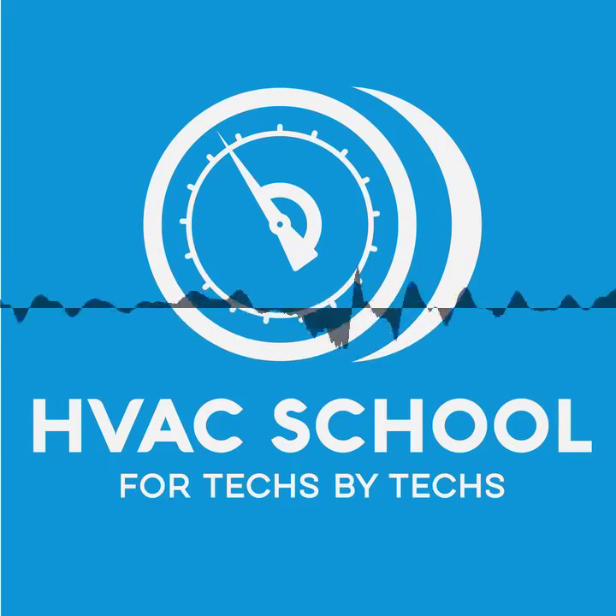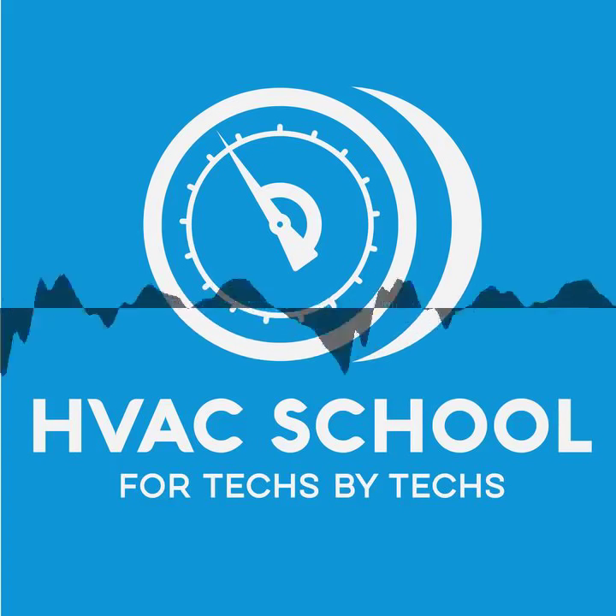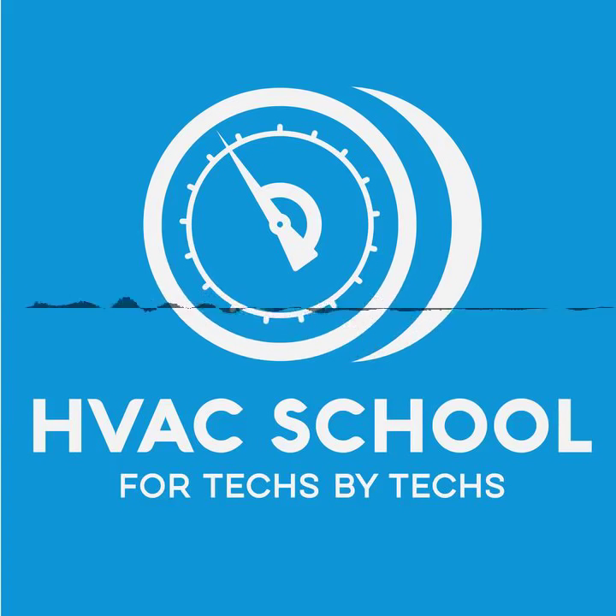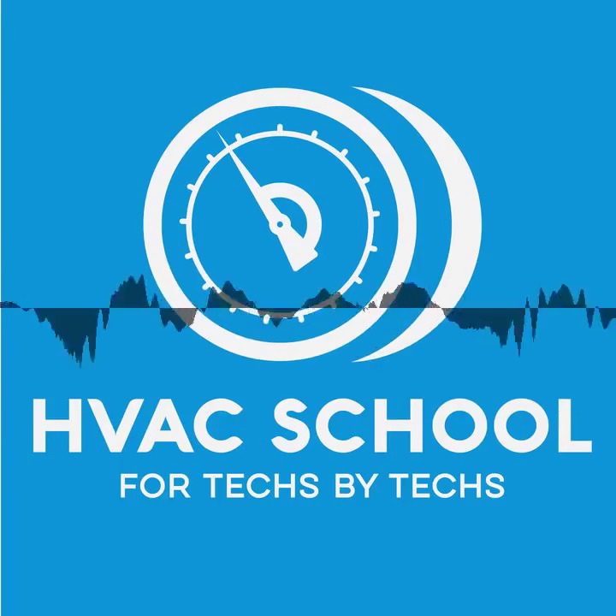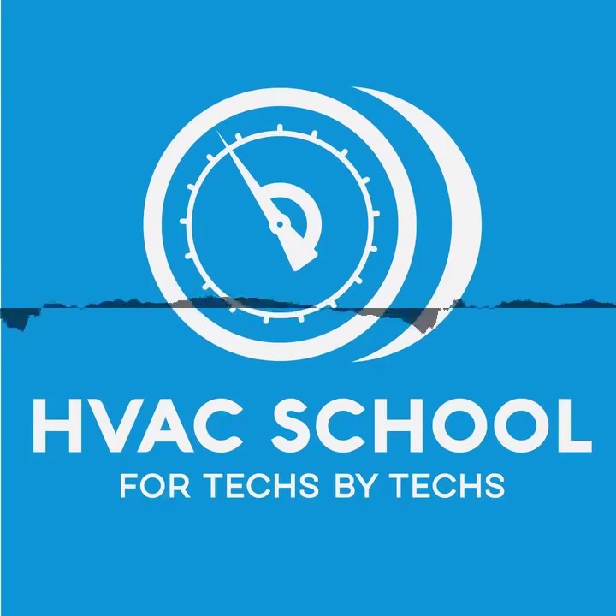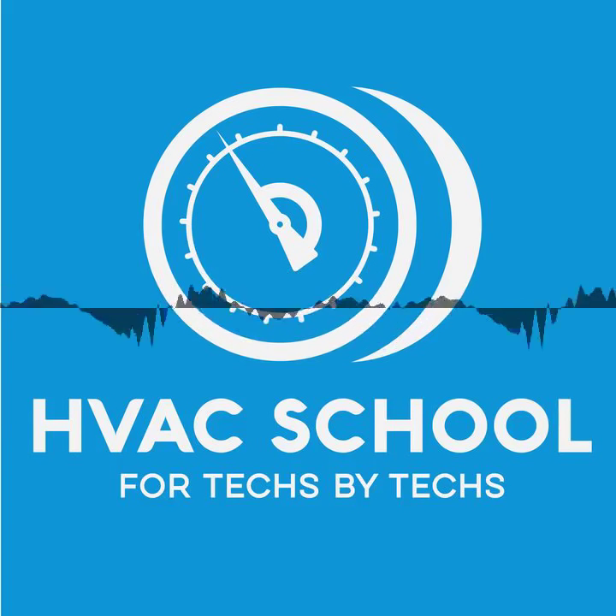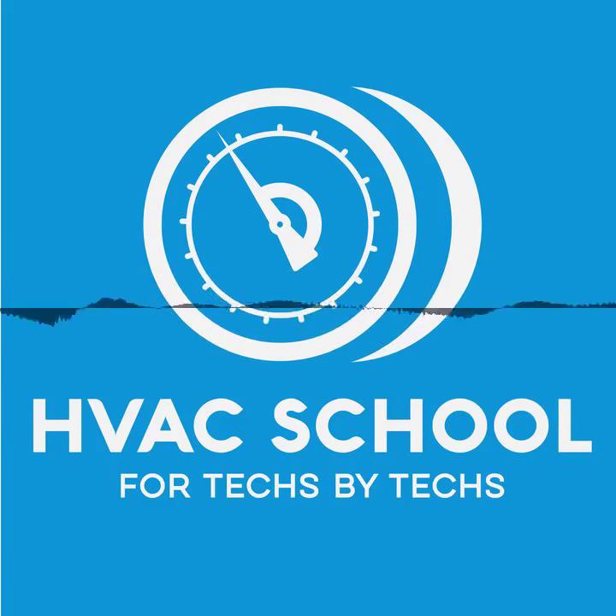Once I pull that contactor out, I'm going to put it on the ohm scale, which is resistance, and I'm going to read across the coil of that contactor. What I'm expecting to see, because I've made the decision that the contactor has failed, is this: it had 24 volts applied to it, so that coil on that contactor solenoid is going to be open, not shorted. Because if it was shorted, it would be blowing the fuse. The fact that it had 24 volts applied and it's doing nothing would mean that it would be open, and when I ohm across it, I expect to see OL, or infinite ohms. I expect to see no path.